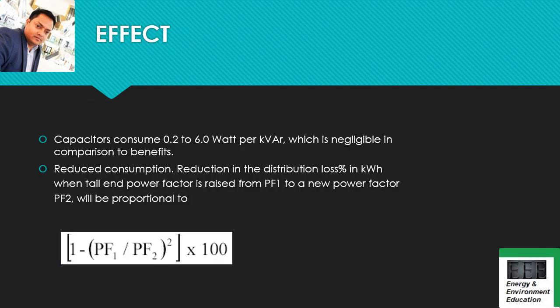The effect of power factor correction — meaning the reduction in energy consumption with correction in power factor — is also very important. The formula is: one minus (under bracket, power factor one divided by power factor two, squared) into 100. Here power factor one is the initial power factor before correction, and power factor two is the corrected power factor after correction. For example, if the power factor was initially 0.80 and was corrected to 0.95, this formula gives you the reduction in energy consumption. This can come in examination as a short type or formula-based question.